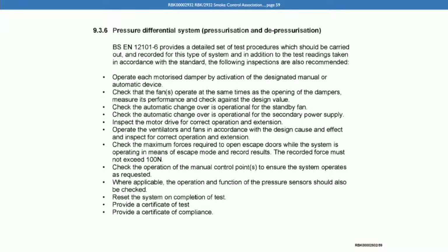So we can see that list. And we can see the 6th bullet point is checking the maximum forces required to open escape doors while the system is operating in means of escape mode and record results. The recorded force must not exceed 100 newtons.